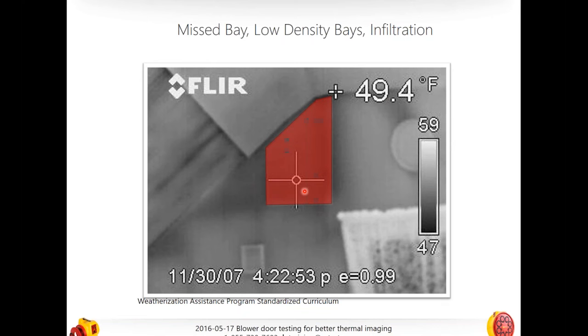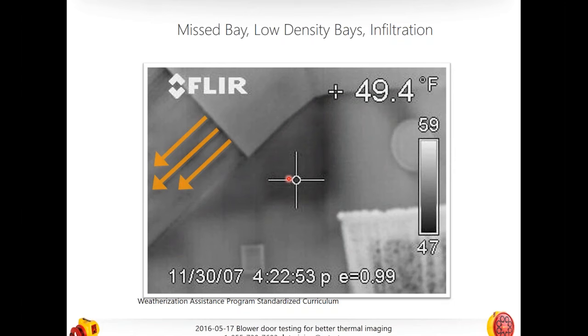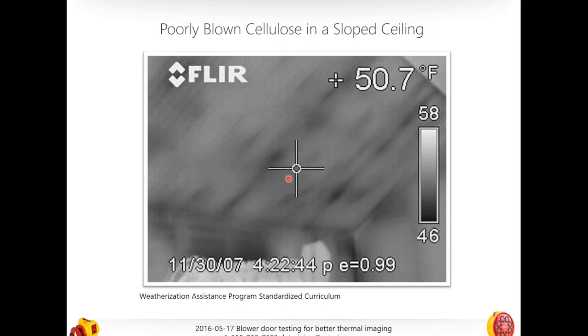The darkest areas indicate an empty wall bay — completely empty. The lighter shade indicates partially insulated bays. You can see from these pictures that some are partially insulated. Here's another very good example of poorly insulated cellulose blown into a slope ceiling. Down at the bottom, in what appears to be a post-beam timber frame house, insulation was blown in from the top and hasn't reached down — probably hit a block or wall blocking.